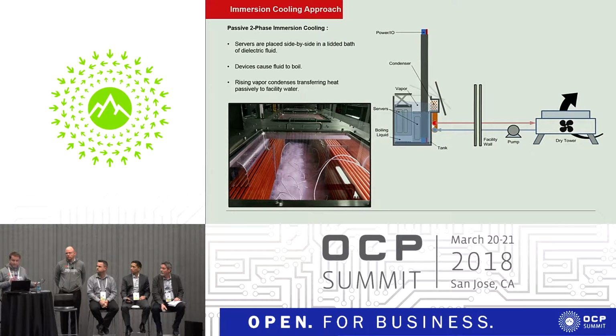People do what we call single-phase immersion with oils and other fluids that do not change state from a liquid to vapor; they're pumped as a single phase. The technology we're talking about in this presentation is two-phase immersion, or evaporative immersion. The hardware is put in a tank of dielectric coolant that boils on the heat-generating components, condenses, and then passively falls back into the tank. Everything that occurs within the immersion environment is passive, and heat is shuttled outside the facility to a dry cooler using conventional water and dry coolers.